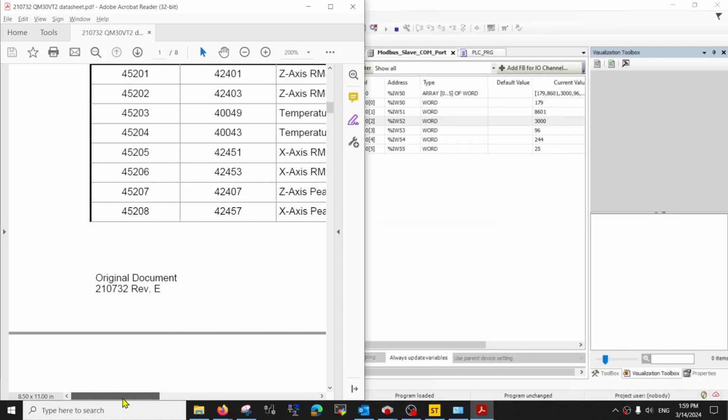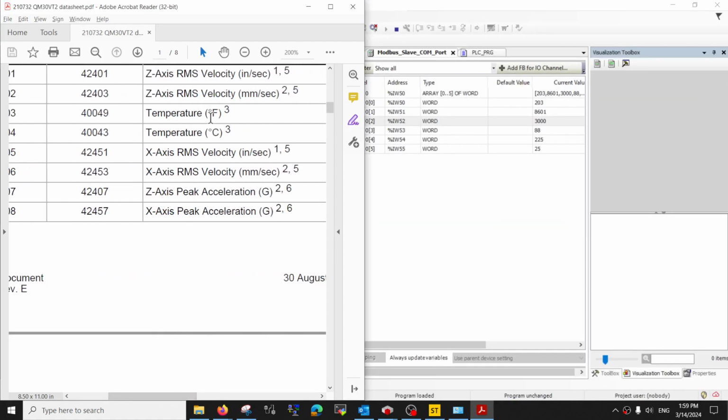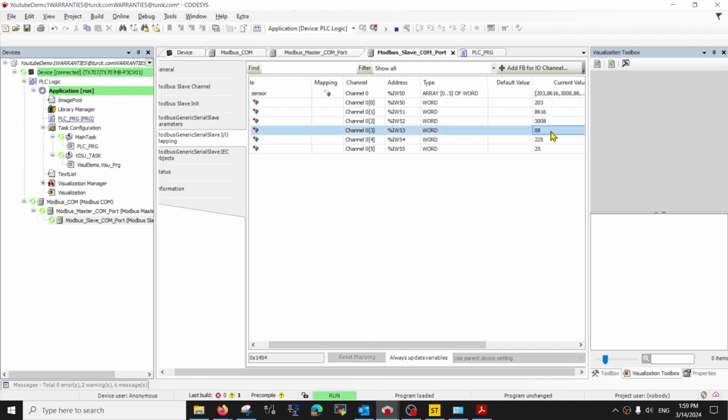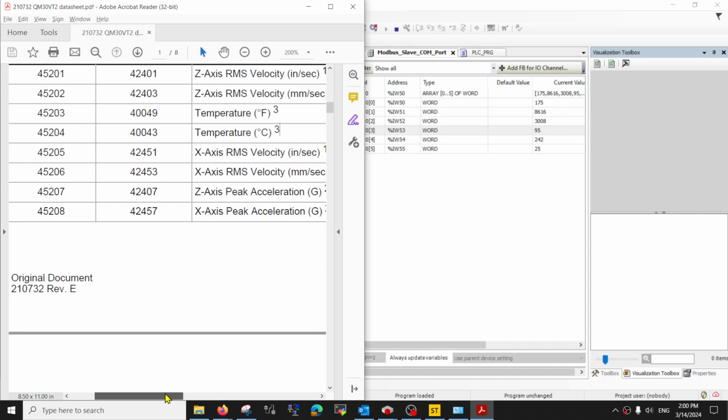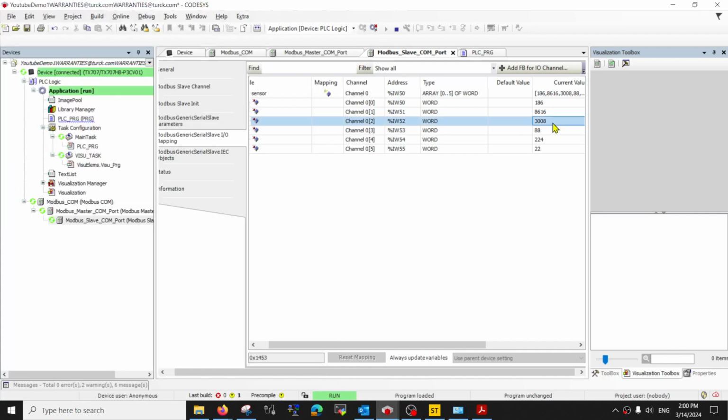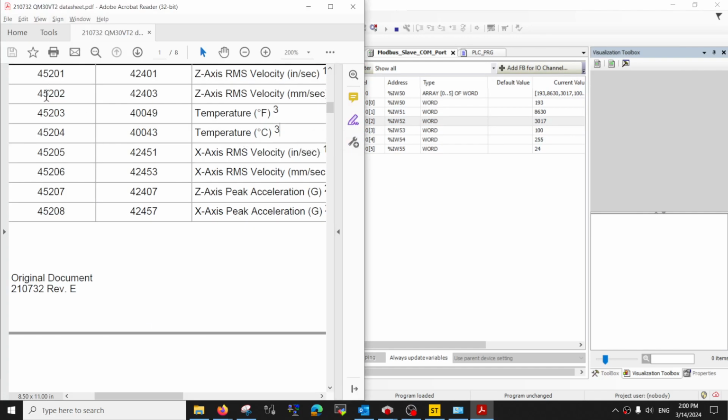You'll notice that I'm supposed to expect my temperature in degrees Celsius on the fourth register, but now it's appearing on my third register. This is my degree Celsius, the third one. Just to further verify, I'm going to shake the sensor, and you realize that the data only increased on the top part. So you can see there is a slight offset in the address value.